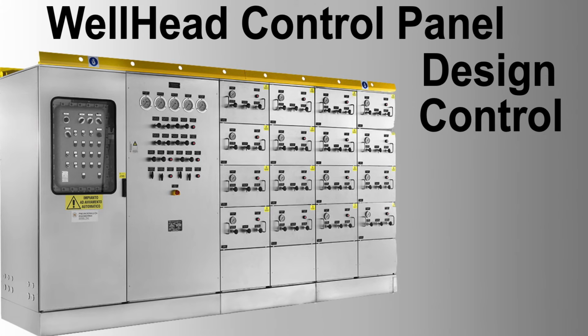Surface-controlled subsurface safety valve, SCSSV, control loop function. The SCSSV is a critical safety device installed downhole to shut off the well flow in case of an emergency. Components: hydraulic actuator operates the SCSSV. Hydraulic control line connects the WHCP to the SCSSV. Pressure transducer monitors the hydraulic pressure in the control line. PLC RTU controls the hydraulic actuator and monitors the pressure transducer.